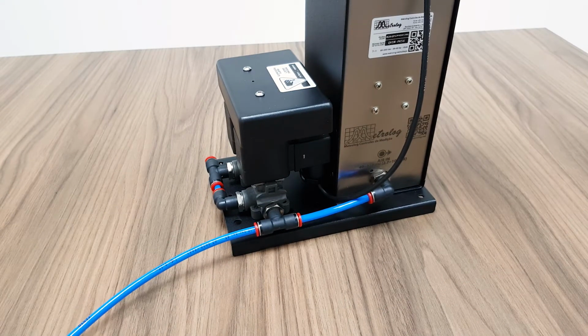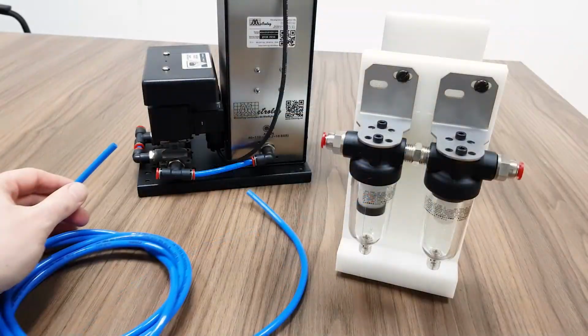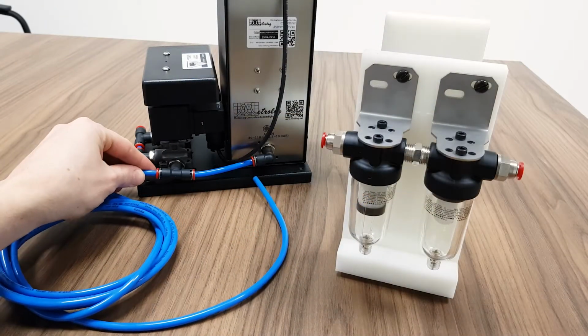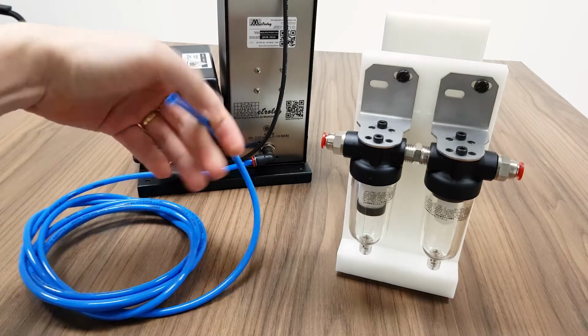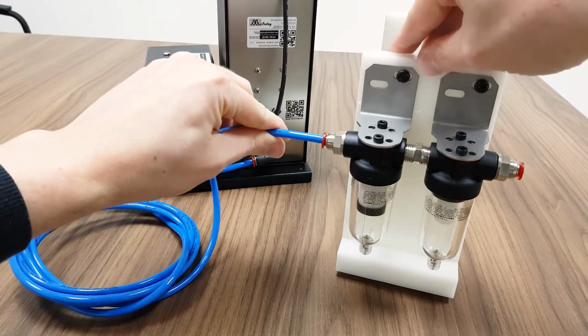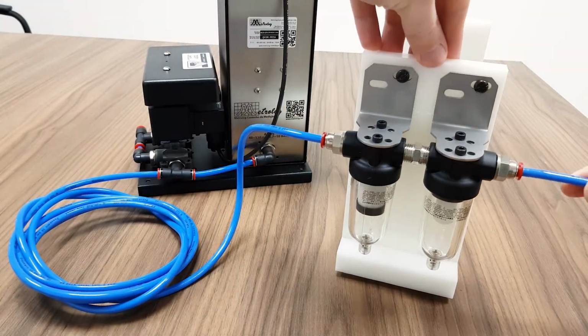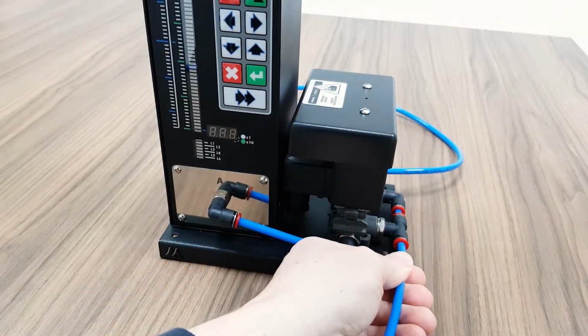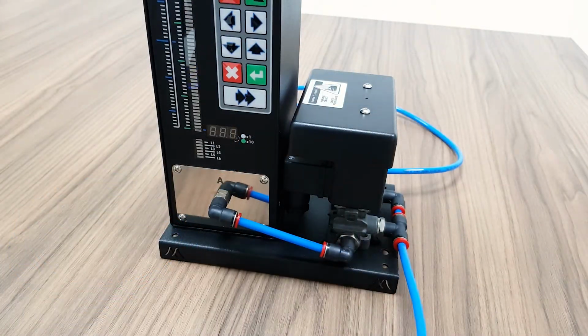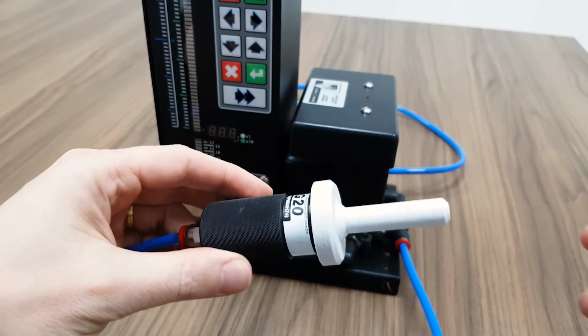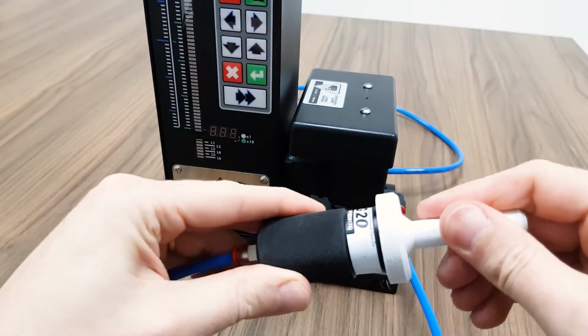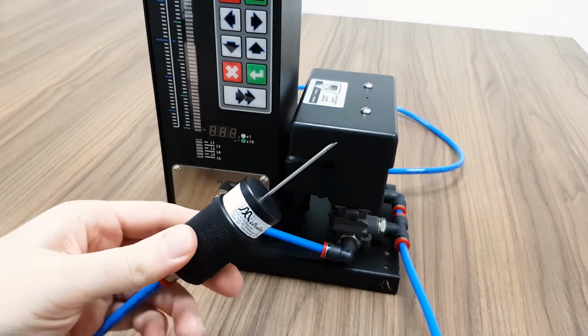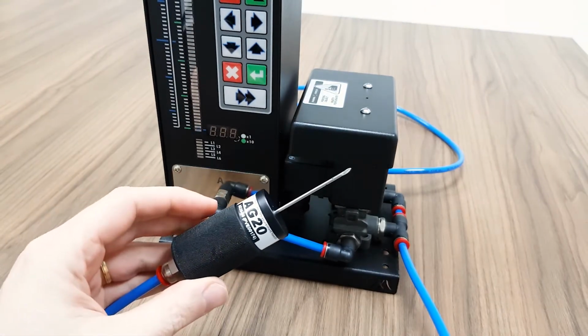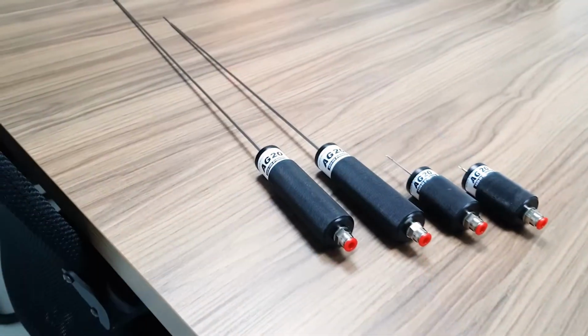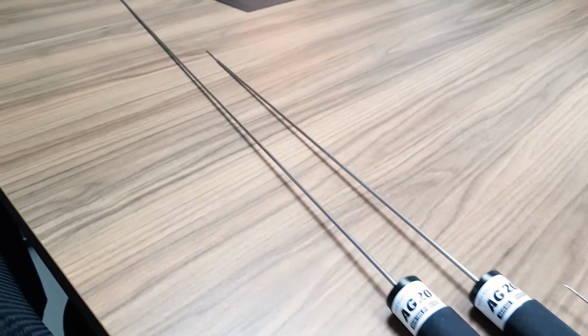The mains pressure should be between 3 and 10 bars. To reduce impurities in the compressed air, it is recommended to install the filters, particulate and coalescing, Metrology F1. For taking measurements, it is necessary to connect a AG20 measurement needle. Needles with a length between 20 mm and 1 meter are available. Different needles allow measurement on small parts and large EPS blocks.